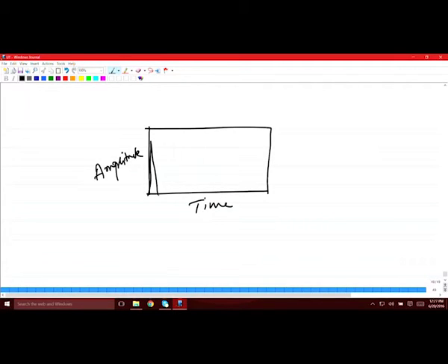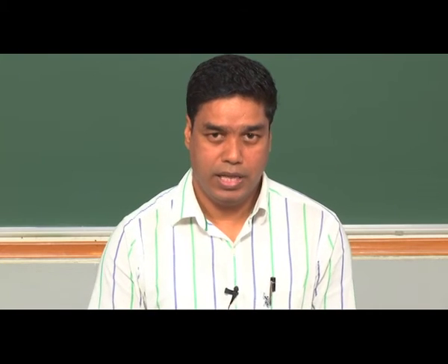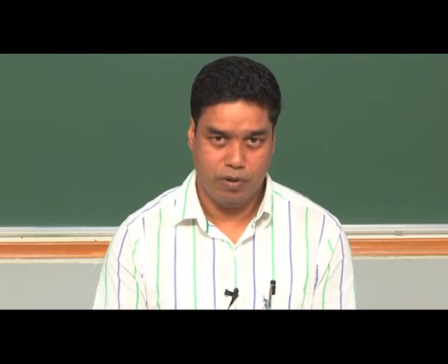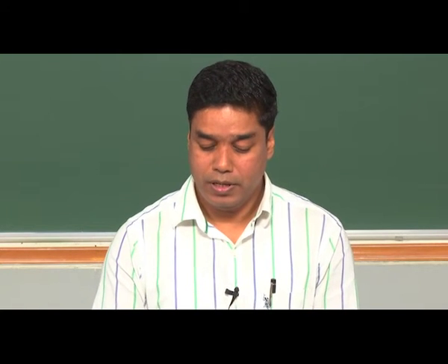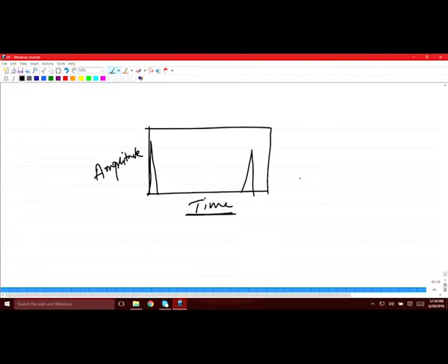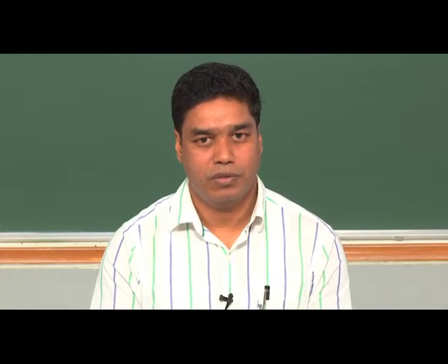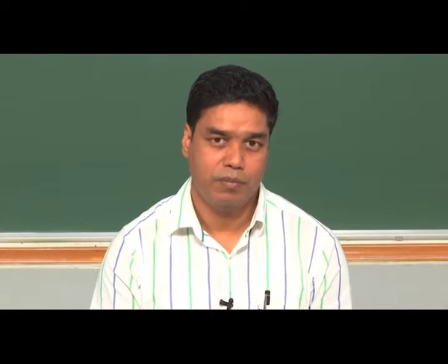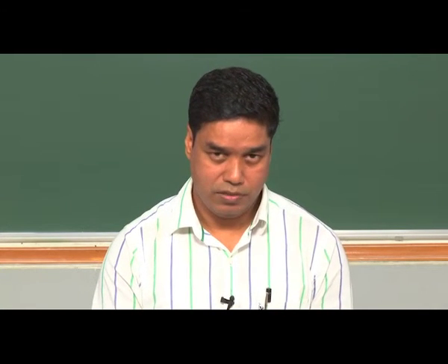so this is the initial pulse, this is the back wall, and the x axis shows you the time at which the echoes come back to the probe. This time can be converted into distance if you know the velocity of sound wave in the material being tested. And most of the time it is known, because in most common metals, alloys and many other materials, the velocity of sound is known.